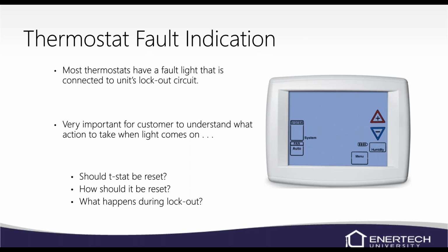One thing that's important with these lockout boards is to understand what the homeowner should do when they do get a lockout. Most of these thermostats now, especially these Wi-Fi thermostats, have the L circuit on the board, which is the lockout circuit. And we have it on our unit to where it'll send a signal to the thermostat to let it know that it's locked out. Now, it's important for the homeowner to understand what they should actually do when that call for service or check system or whatever it says on there.